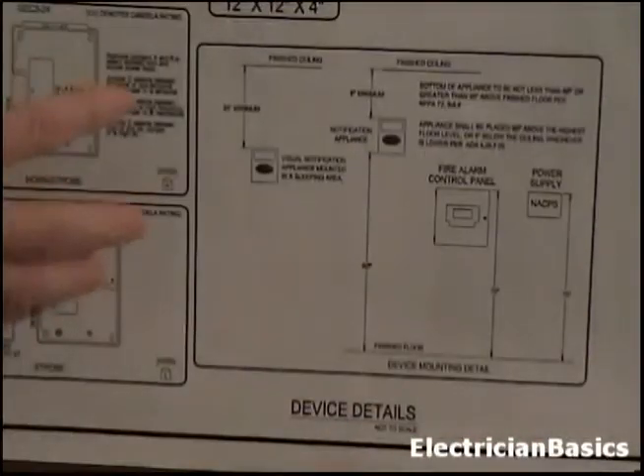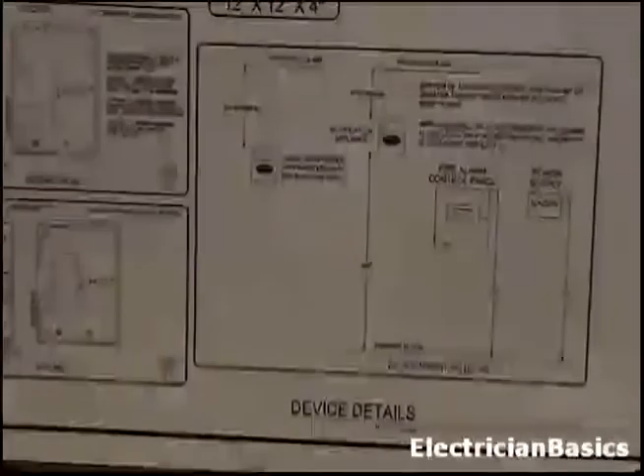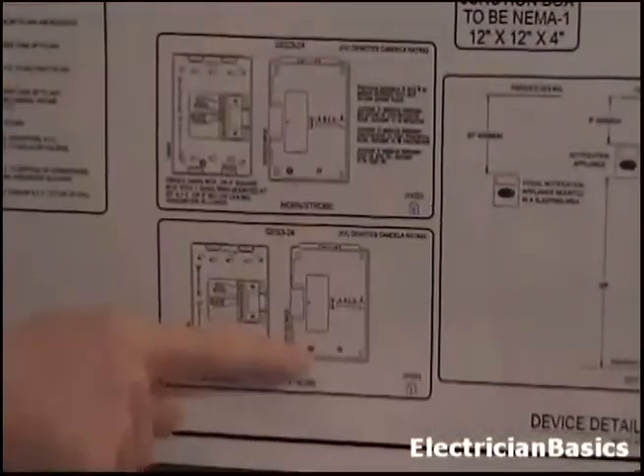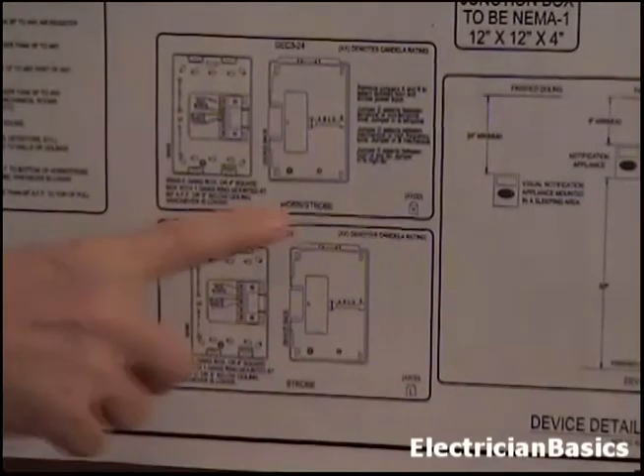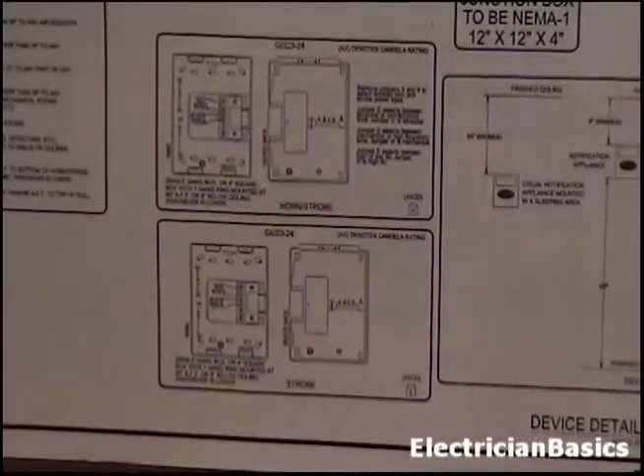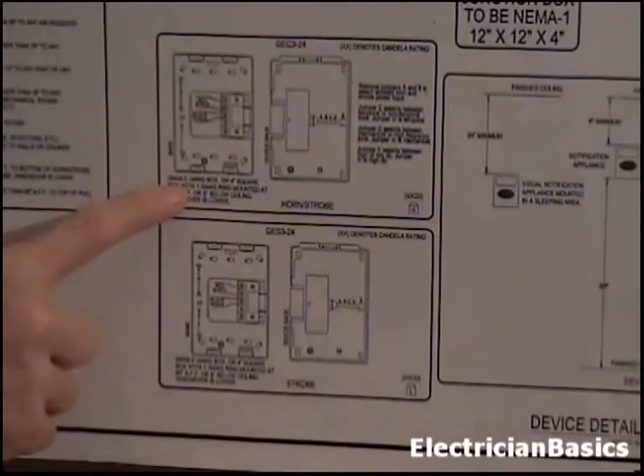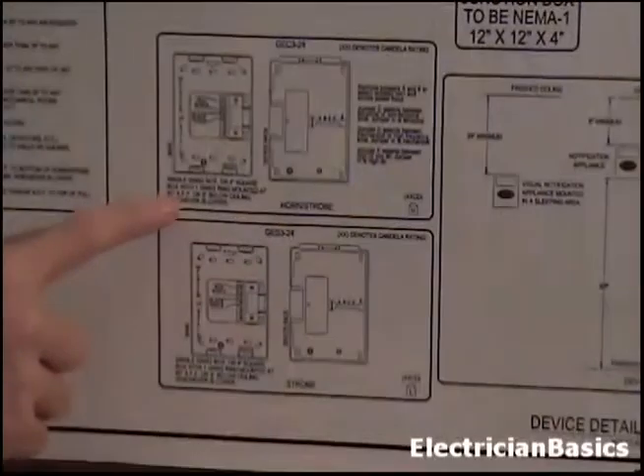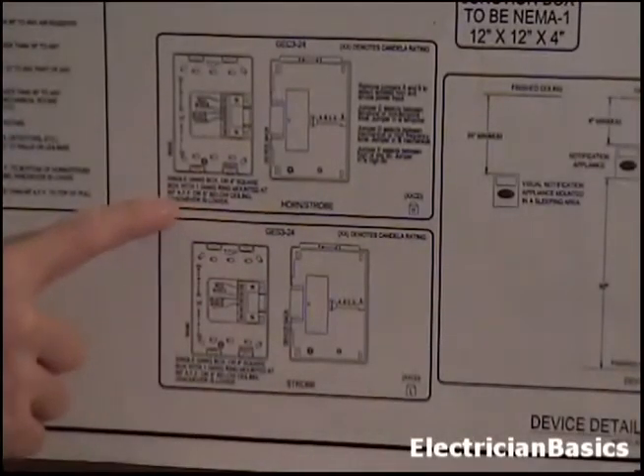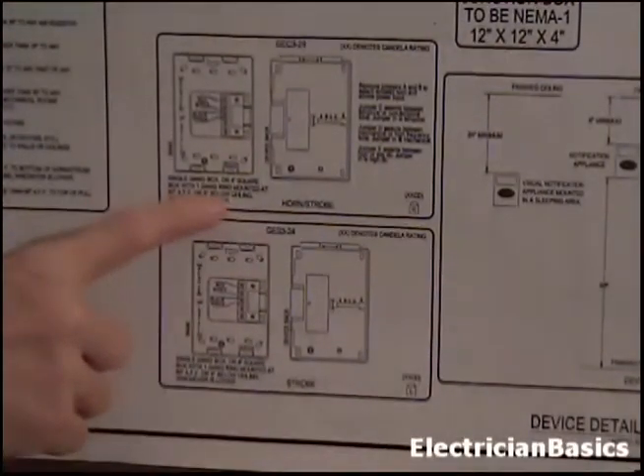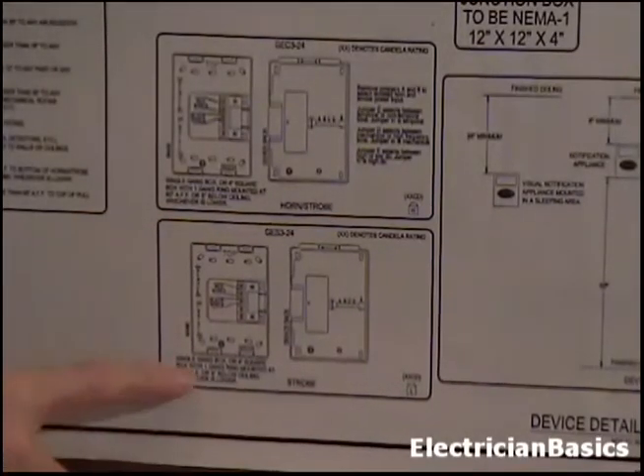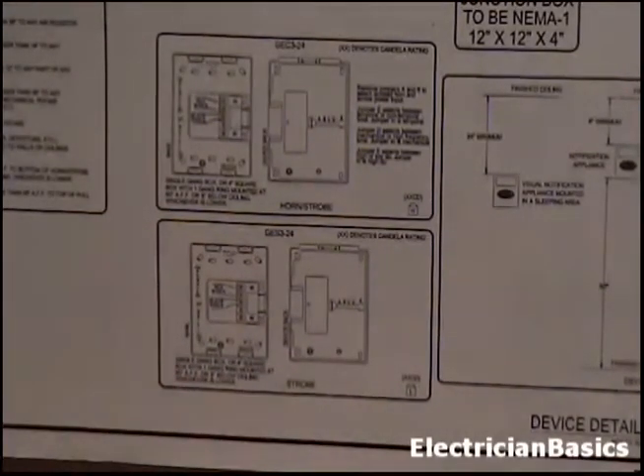Okay, so it's time we're going to move over to some other details on the page. These last two little diagrams here, it says horn strobe and strobe. And these are some simple wiring diagrams. And it tells here, you mount this in a single gang box or 4-square box with one gang ring mounted at 80 inches above finished floor, 6 inches below ceiling, whichever is lower. So we know we're going to put this in a box, same detail here.